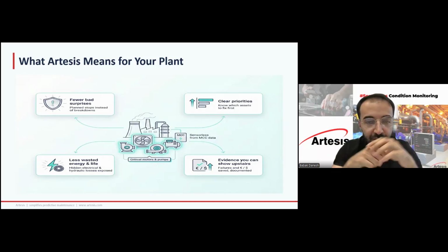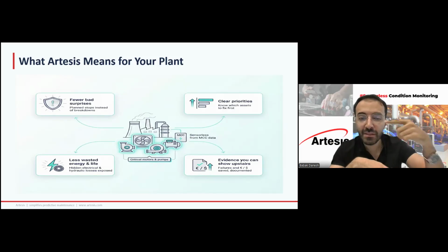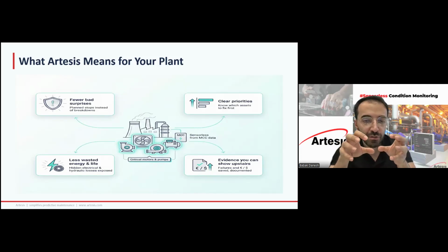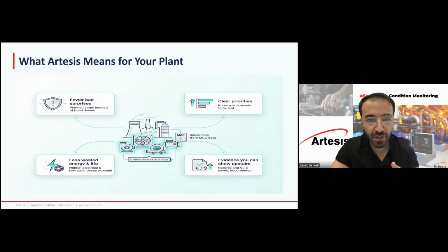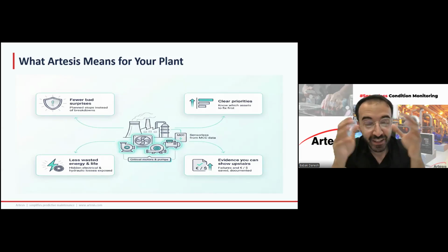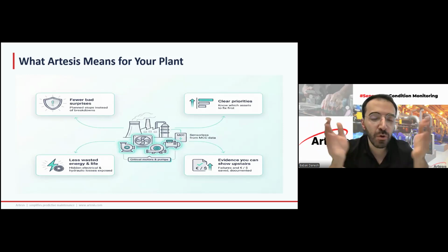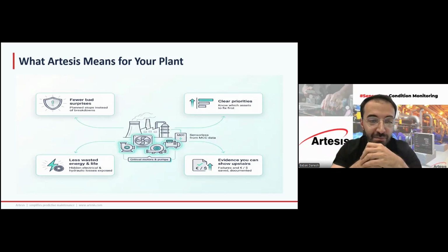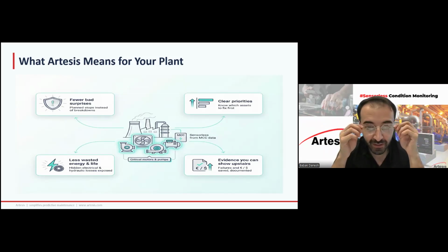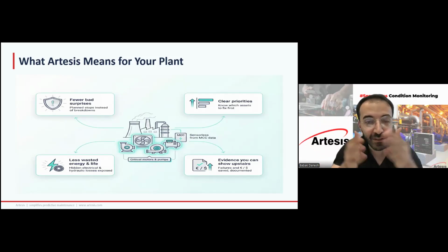For the mechanical issue, I will answer this important question as well, explaining mechanical faults in detail. As you saw so far, with vibration you mostly can detect mechanical faults. But how do you know the data of VFD, electrical losses, grid quality, external faults or internal faults like insulation related problems, rotor related problems, winding problems, stator faults? All of them are really huge problems, and what mostly the reliability and maintenance team encounter in the field, and the team's nightmare, are these faults mostly.